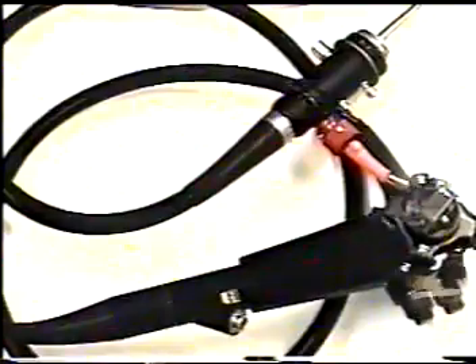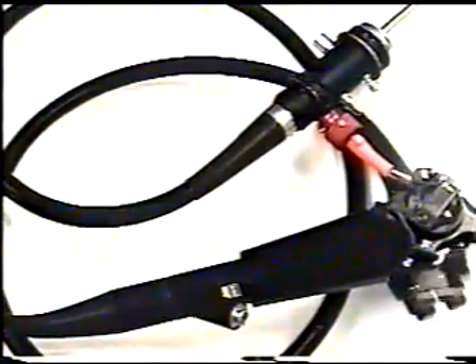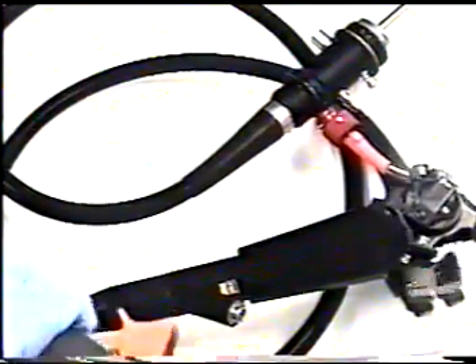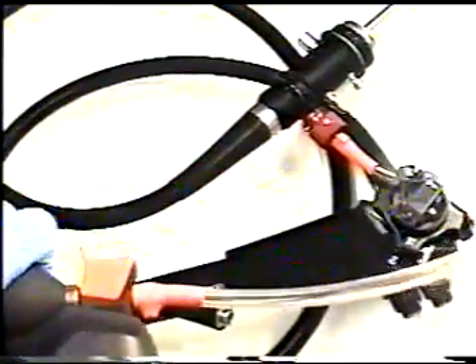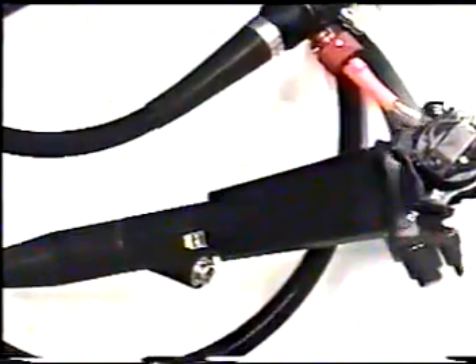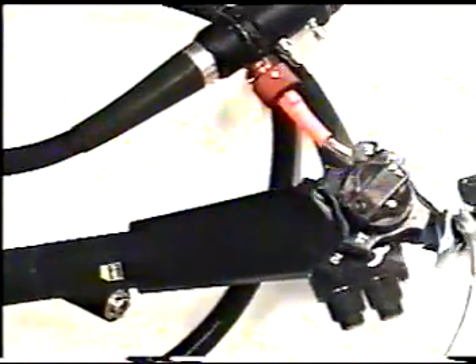Clean any grease or dirt that might have accumulated on the insertion tube, only using tissue and alcohol or soap and water. Once angulation control adjustments are made, we'll need to airtight test the instrument with a handheld airtight tester, pumping up the endoscope and checking all body covers that we have just opened are not leaking at all, including the entire rest of the endoscope.